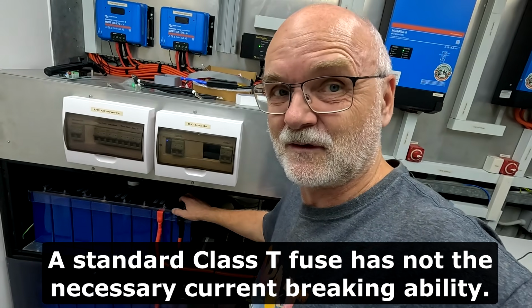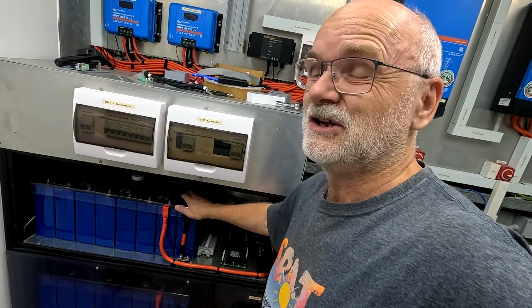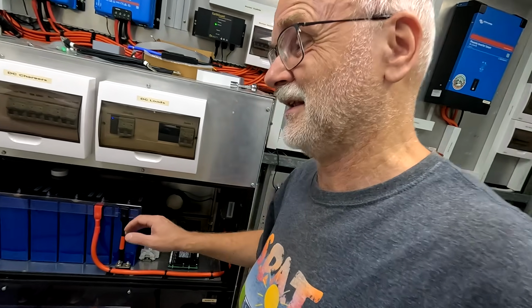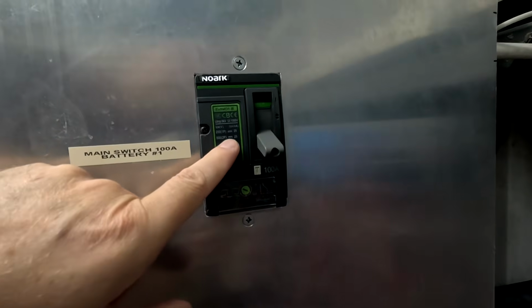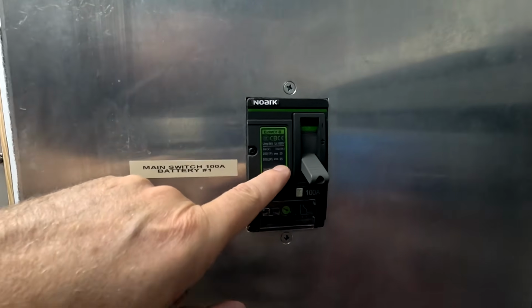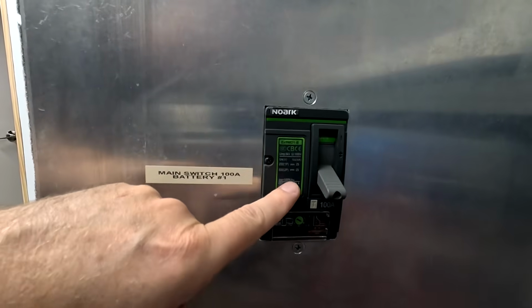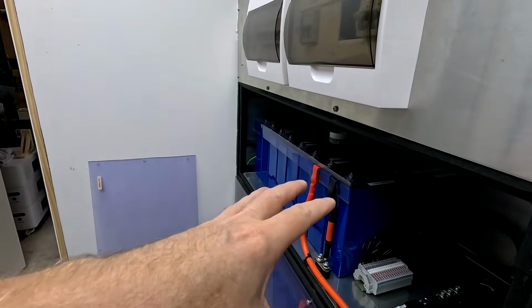Because the internal resistance of these batteries here is so low, you should always use a fuse as well. Even this breaker has 25 kiloamps of breaking capacity, it may not be sufficient to actually disconnect this battery safely here.